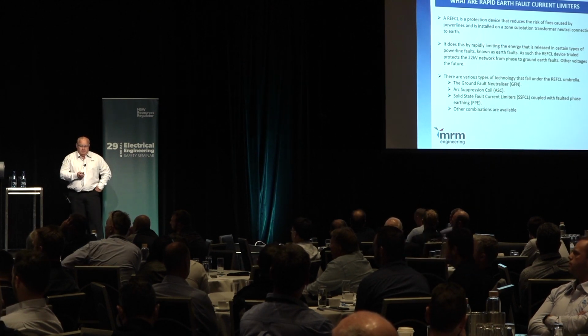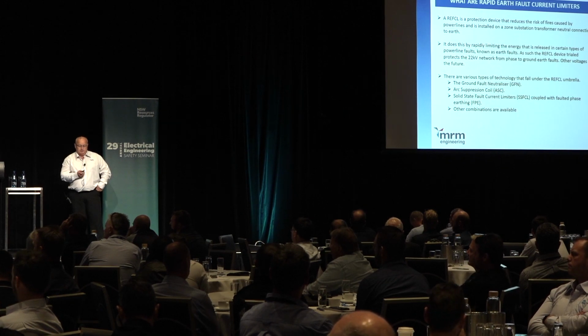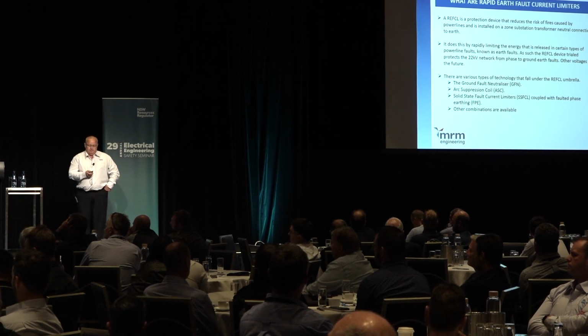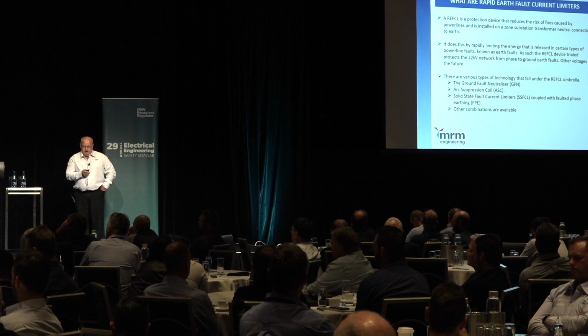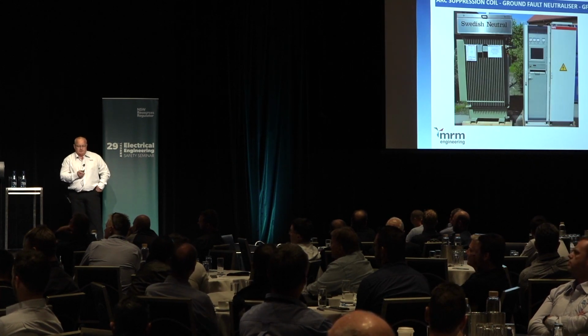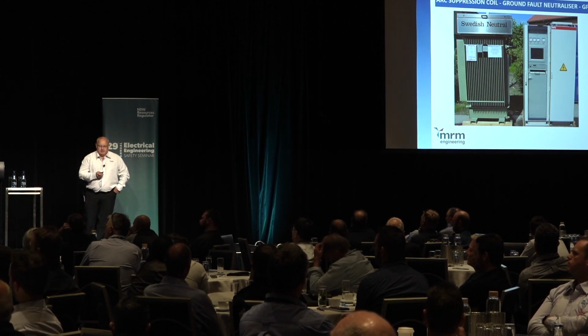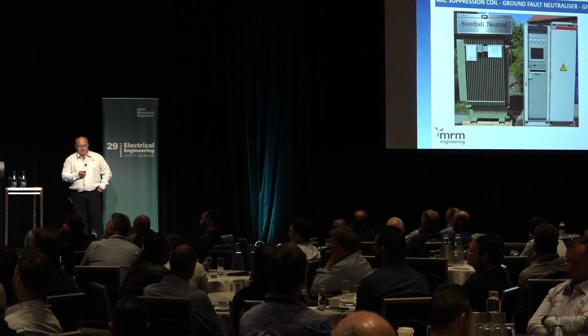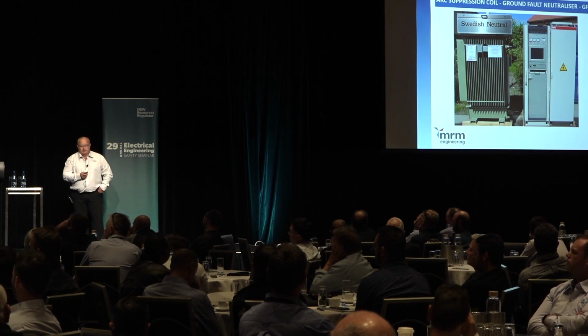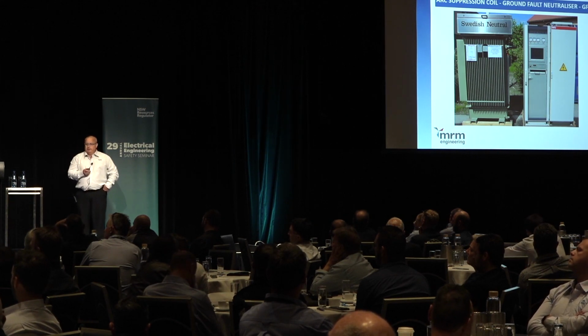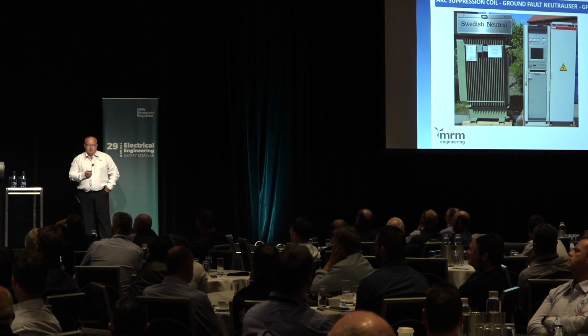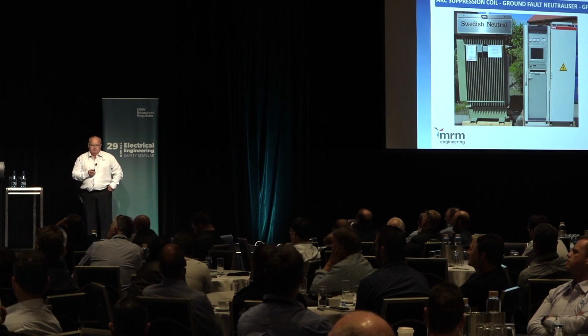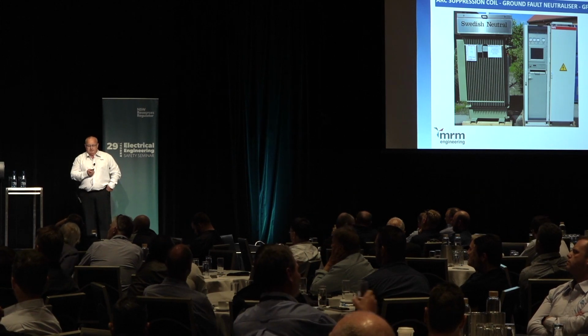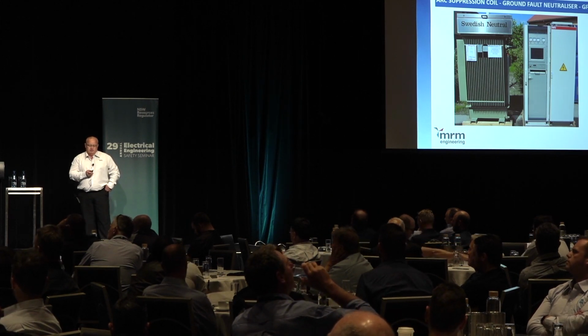Some of the technology is a ground fault neutralizer, arc suppression coils, the solid state current limiters, and there are obviously other combinations around as well. So we'll go through the technology of these things now. This one's an arc suppression coil, or a ground fault neutralizer. What it is, is an inductor hooked into the neutral connection, with a specific controller to control it. Back in the original days, they were called Peterson coils. The Petersen coil was a fixed inductance which tried to match the line capacitance. The modern ones now are dynamic, so they can actually change the inductance as the system network changes.